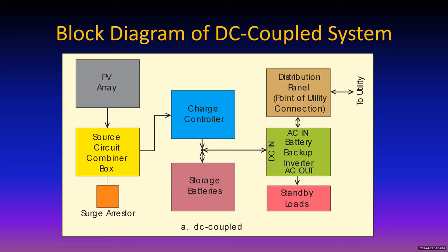But typically, we're looking at something like somewhere between 150 and 600 volts and about 10 amps for each series string of modules. So in a way very similar to a way a distribution panel works, where the utility comes in with fat wires and the loads are connected with thin wires. In this case, the solar comes in with skinny wires and leaves the source circuit combiner box on fatter wires.